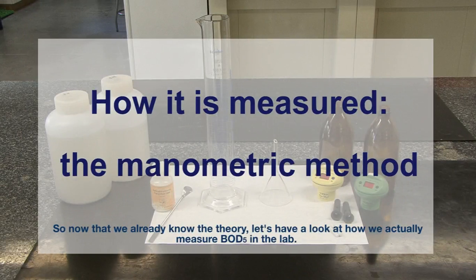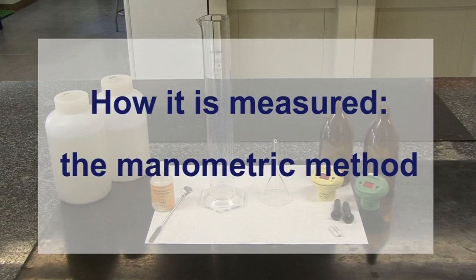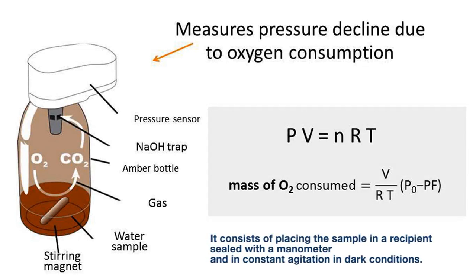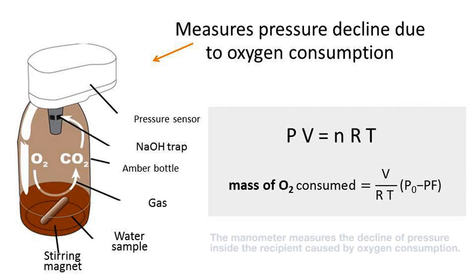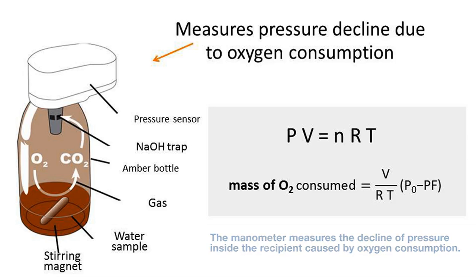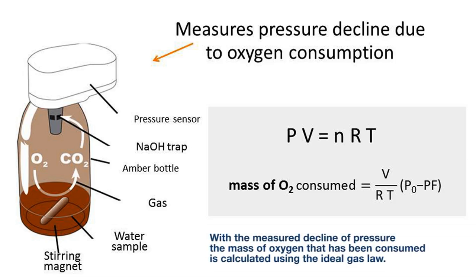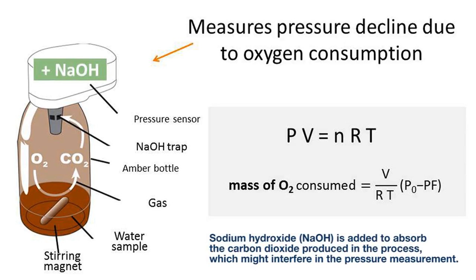Now that we already know the theory, let's have a look at how we actually measure BOD5 in the lab. It consists of placing the sample in a recipient sealed with a manometer and in constant agitation in dark conditions. The manometer measures the decline of pressure inside the recipient caused by oxygen consumption. With the measured decline of pressure, the mass of oxygen that has been consumed is calculated using the ideal gas law. Sodium hydroxide is added to absorb the carbon dioxide produced in the process, which might interfere in the pressure measurement.